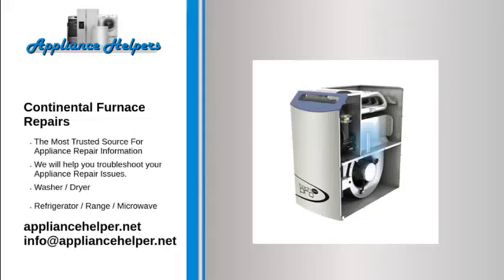On condensing furnaces, if the burners come on for longer than 5 seconds but turn off before the thermostat is satisfied, the condensate drain could be plugged. Most of these units have a built-in trap and sediment can build up in it. This can cause the furnace to operate abnormally.